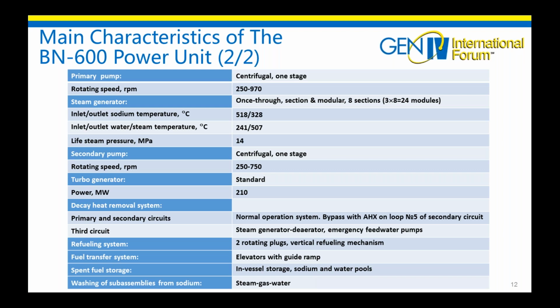We have a standard turbo generator with a power of 210 megawatts. We have a decay heat removal system. It is located in bypass, with an air heat exchanger on the loop of the secondary circuit. Our refueling system is made of 2 rotating plugs, and we have a vertical refueling mechanism. We have 3 spent fuel storages. One of them is in-vessel storage, the second is the intermediate sodium storage, and the last one is the water pool. We wash our assemblies from the sodium with steam, gas, and water.